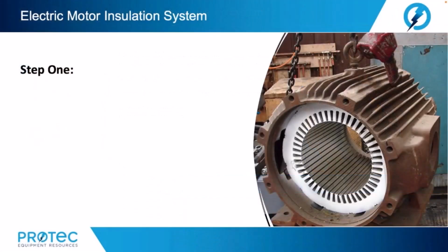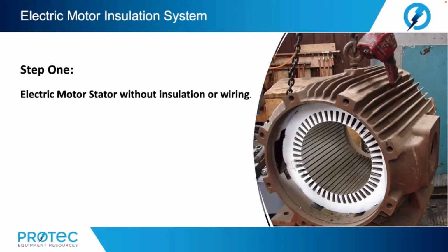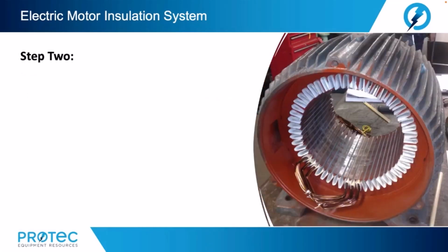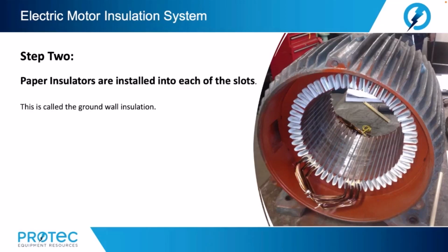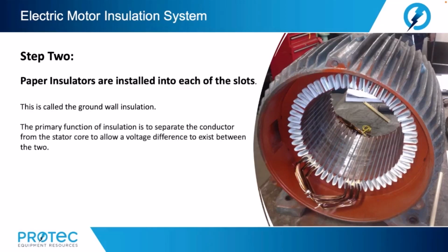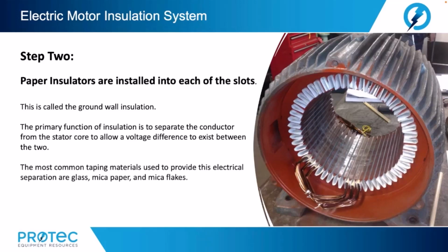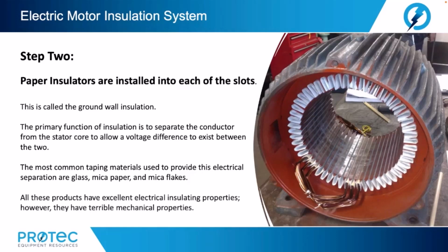So, step one. The electric motor stator is without insulation or wiring. In step two, paper insulators are installed into each of the slots. This is called the ground wall insulation. The primary function of insulation is to separate the conductor from the stator core to allow a voltage difference to exist between the two. The most common taping material used to provide this electrical separation are glass, mica paper, and mica flakes. All of these have excellent electrical insulating properties. However, they have terrible mechanical properties.